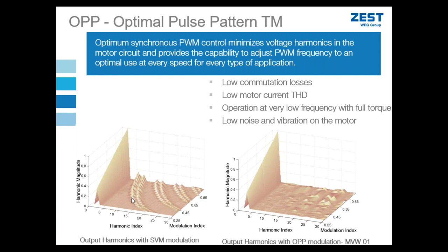And you can see from the diagrams that it has a dramatic improvement. This diagram compares space vector modulation versus optimal pulse pattern switching, which uses space vector modulation but tells my drive exactly which are the optimal vectors to use, and it compares them with relation to harmonics. This first harmonic profile is the harmonic magnitude of my fundamental with respect to my modulation index. Remember earlier we said we increase our modulation index from 0 to 1 as we increase my drive speed from 0 to full speed. We already discussed that we have an increase in the harmonic magnitude as we increase our modulation index. That can clearly be seen here, and that is normal, so we don't want to change that. In both scenarios, we have that same situation.